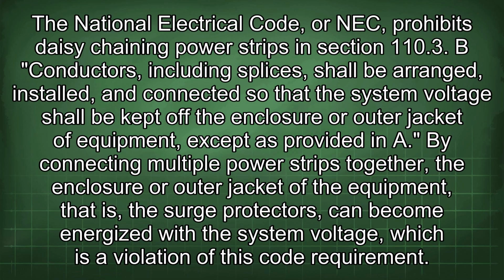The National Electrical Code, or NEC, prohibits daisy chaining power strips in section 110.3(B): conductors, including splices, shall be arranged, installed, and connected so that the system voltage shall be kept off the enclosure or outer jacket of equipment except as provided in A. By connecting multiple power strips together, the enclosure or outer jacket of the equipment, that is, the surge protectors, can become energized with the system voltage, which is a violation of this code requirement.